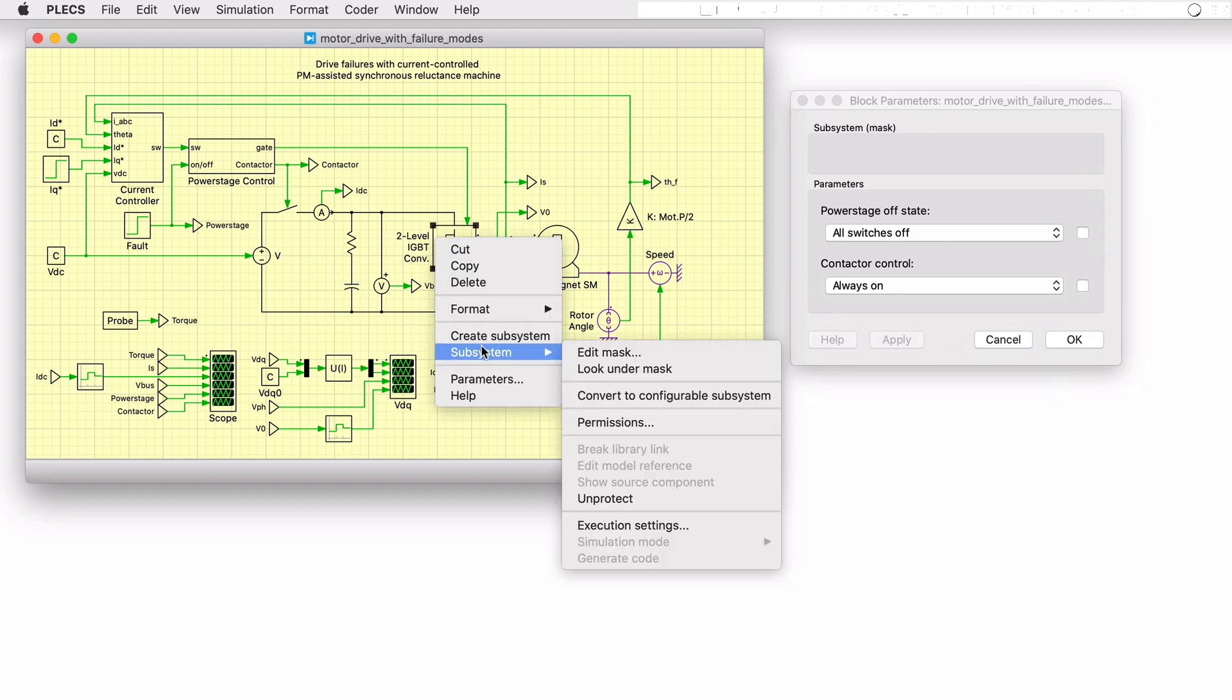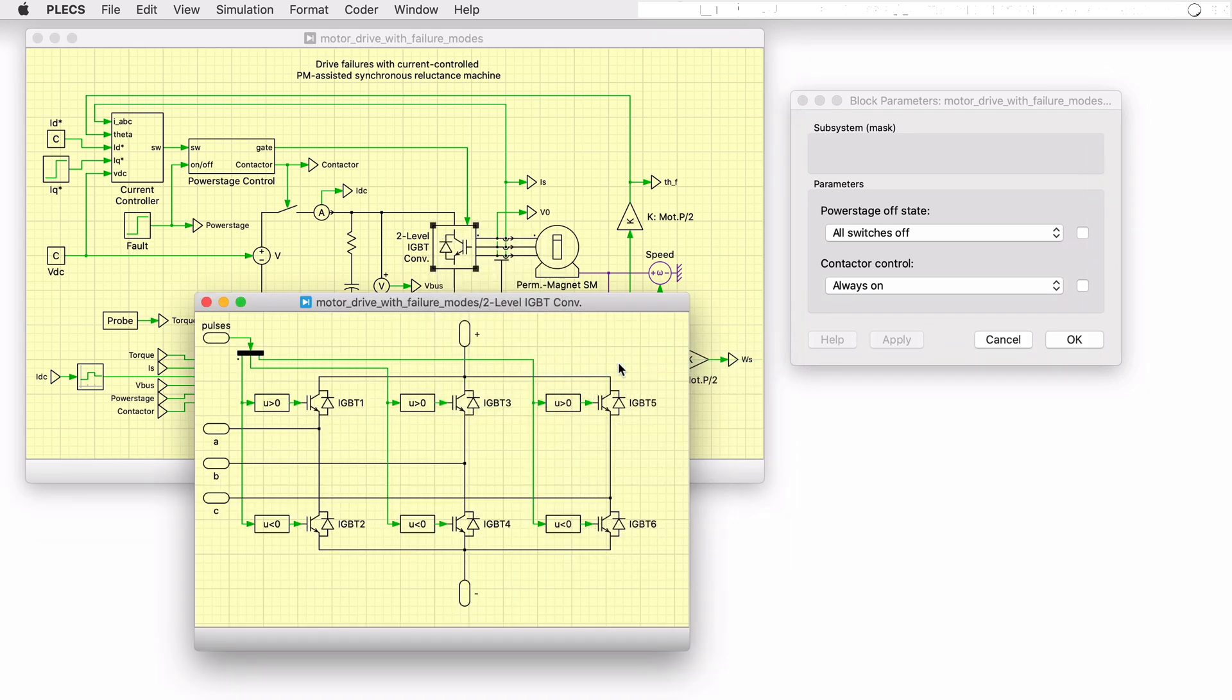Another fault mitigation strategy is to short the machine phases by closing all the lower switches of the inverter. The back EMF of the machine would result in large motor currents that would produce a decaying oscillatory torque.